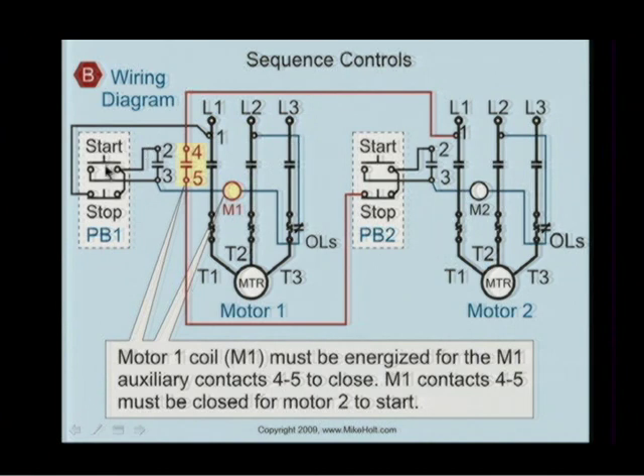Let's go. You press the start button. Now I got voltage going to one side of the coil. Come over here, goes to the stop button. I get voltage to the start button. I press the start button. I get voltage over to the M coil. Energize the M coil. I close the 2 and 3 point, which continues the voltage, that's the interlocking contact. It's the auxiliary contact that's interlocking, right?